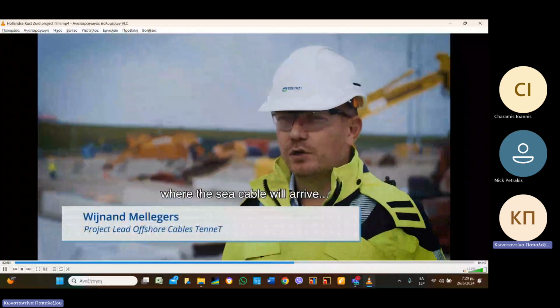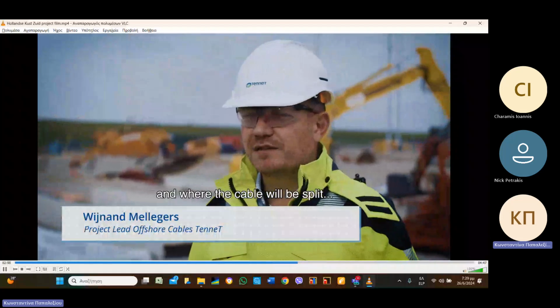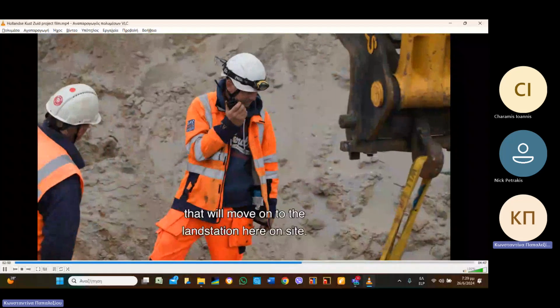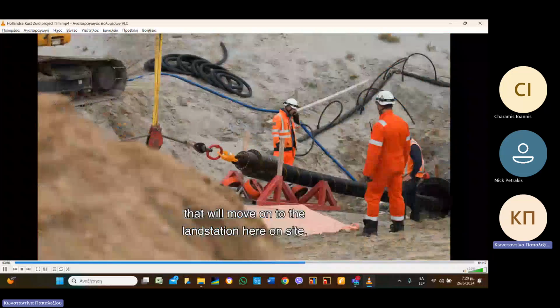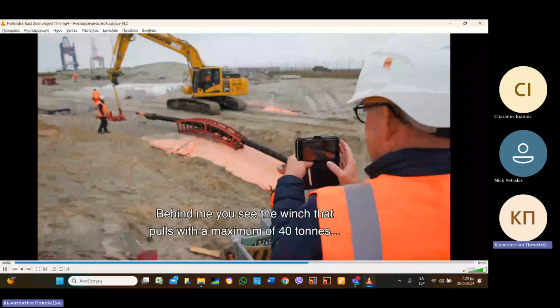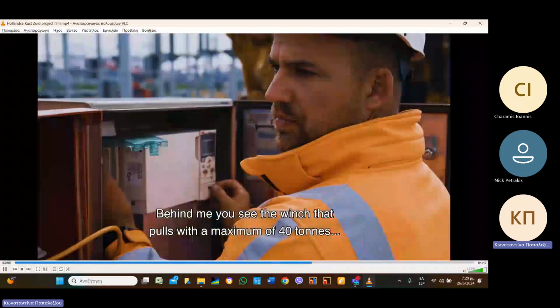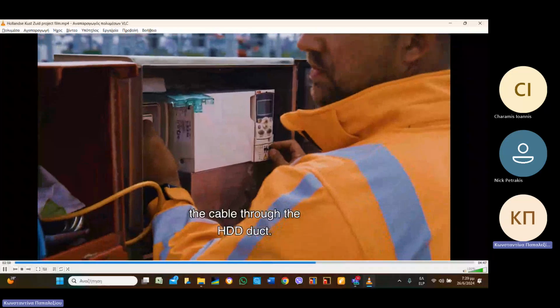You see here the pull-in pits where the sea cable will arrive and where it will be split into 3 separate cables that move on to the land station on site. Behind me is the winch that pulls with a maximum of 40 tons, drawing the cable through the HDD duct.